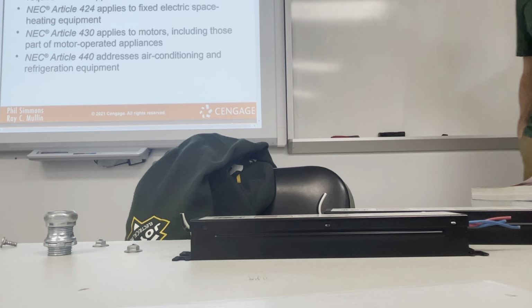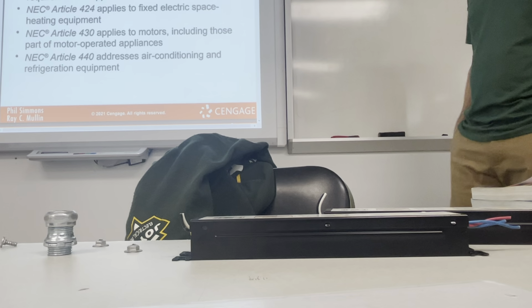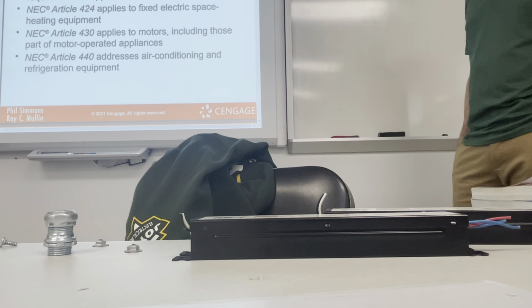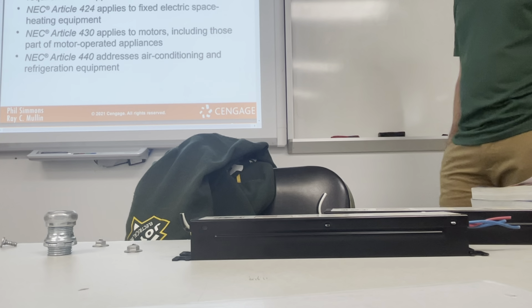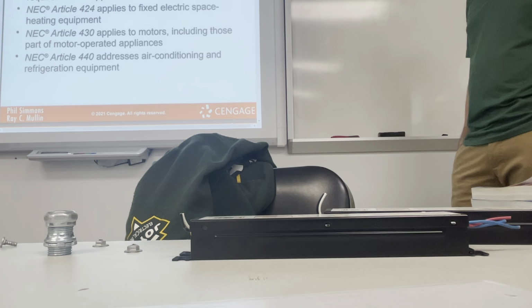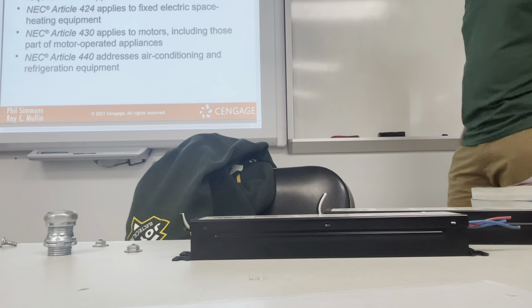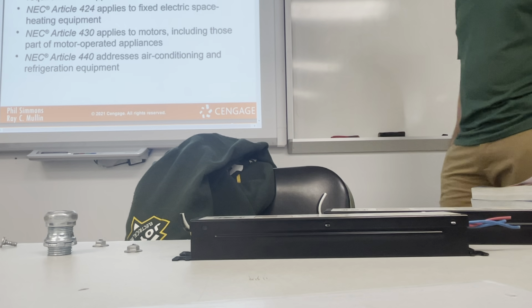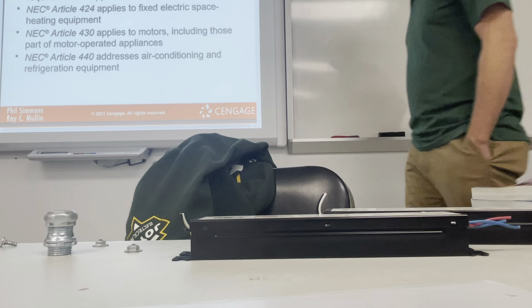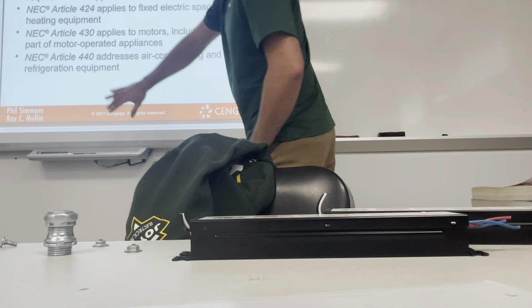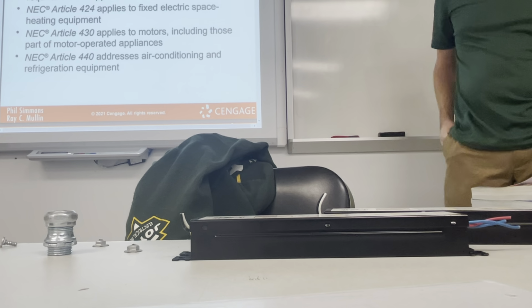NEC Article 422 sets forth the installation requirement for appliances. NEC Article 424 applies to fixed electric space heating equipment. NEC Article 430 applies to motors, including those part of motor operated appliances. And NEC Article 440 addresses air conditioning and refrigeration equipment. All right, so there's a lot of articles that set forth for specific areas. We're talking about hooking up appliances.